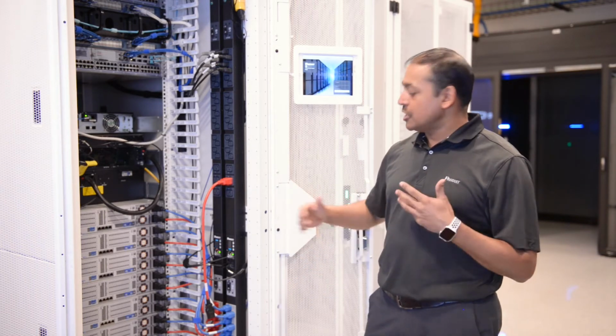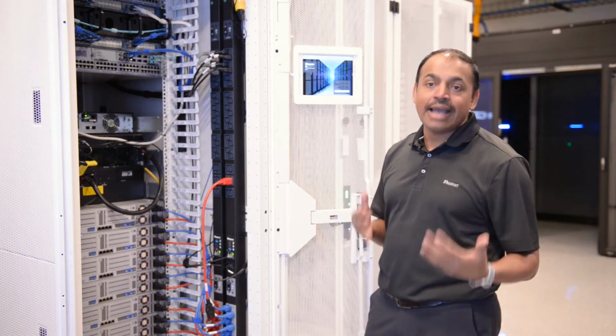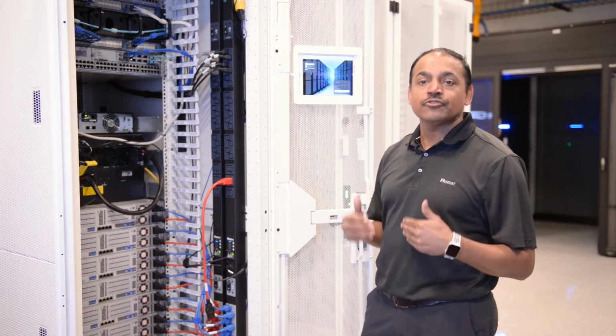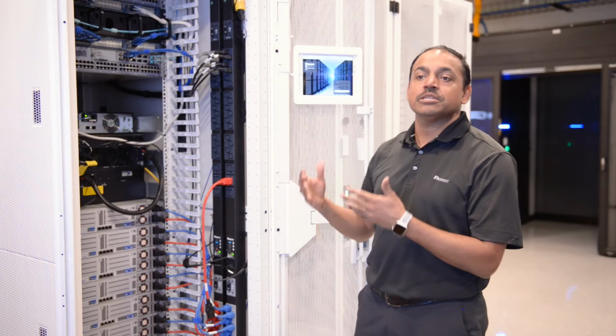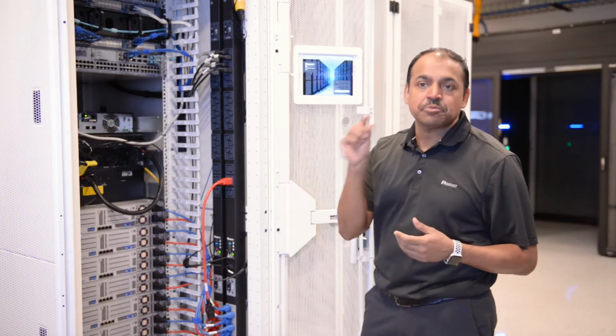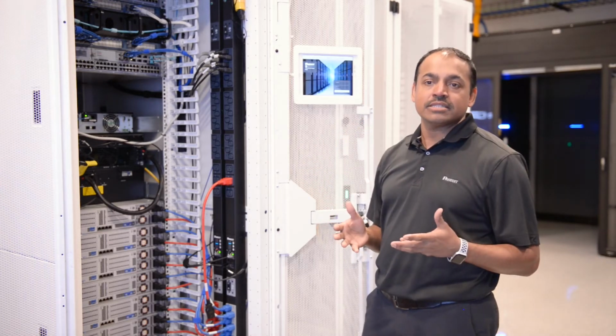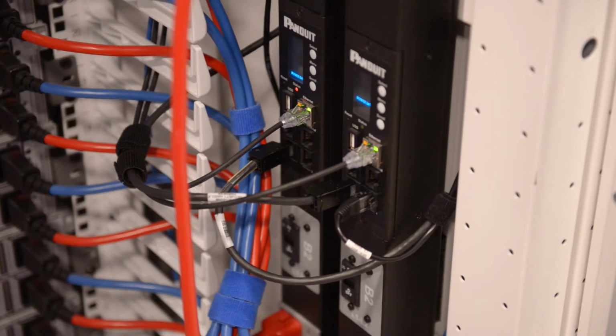What we recognized is that data switches in the data center no longer auto-negotiate below gigabit speeds. As a result, you can get a PDU to run at 10/100, but you've got to spend labor having somebody go into that switch, into that specific port, and set it to run at 10/100. With our product featuring Gigabit Ethernet, it's a plug-and-play solution, resulting in additional labor savings for the customer.